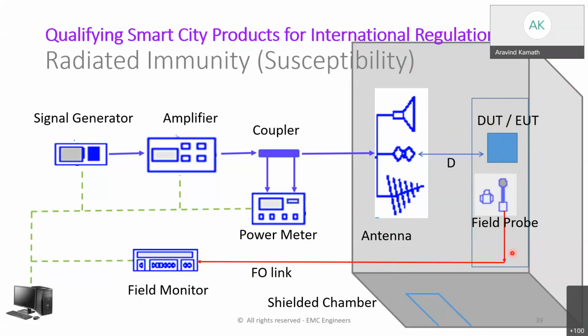Why a shielded chamber? Because you don't want outside world signals to affect your equipment. You want only intended signals to affect your equipment. That is why there is a chamber. So you radiate on your equipment and see whether it will misbehave or not. There are fiber optic probes. Through the fiber optic link, it goes to the field monitor meter. The field monitor meter will measure the field. This is the typical setup.